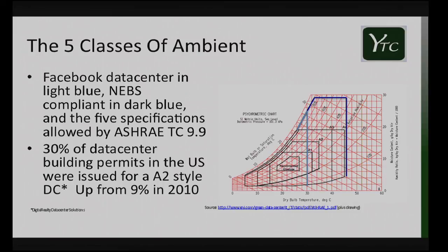This is the ASHRAE chart - the dark blue line going way up top represents NEBS compliant setups, like telco points of presence. Facebook's setup is this light blue one, among others. The 'recommended' range in the center is the old method data centers used to run; now the tolerances go much wider. An A1 facility just adds panels and baffles to separate hot and cold aisles. A2 generally means hot aisle containment while keeping the rest of the data center cool - around 25-30°C, 90°F - which is considered cool in data centers nowadays.